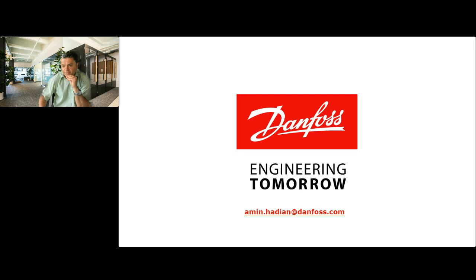Yeah, but I know that there are regular test runs to check that the system is still working and that the pump starts and so on. So that is done on a regular basis, and the system integrators have to follow that. Those who just integrate the pump in their pump unit and make the complete pump system have to obey those regulations and those regular tests, I believe, which is highlighted in the related documents.